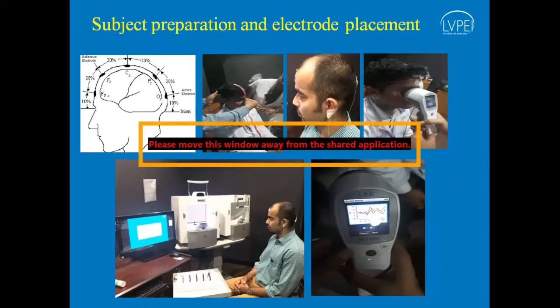This is how the setup looks. There are single channel and multi-channel protocols, but the ISCEV recommendation is single channel midline electrodes. So this is how electrodes are placed. The active electrode is placed over the occipital cortex, overlying the visual cortex. And the ground and reference electrodes can be put on the frontal region, overlying the frontal cortex, and either the mastoid process or earlobe.